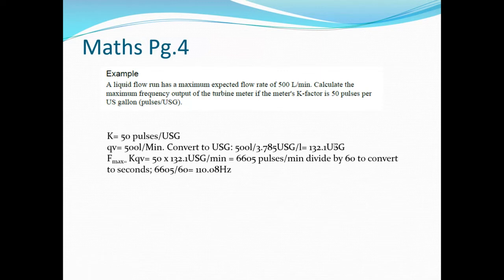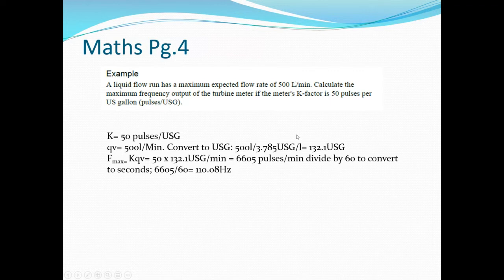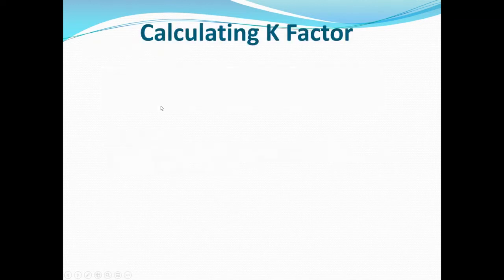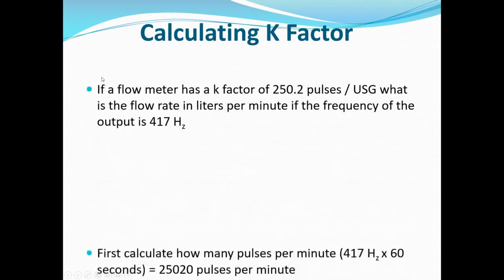Since frequency is counted in seconds, we convert: 50 pulses/gallon times 132.1 gallons/minute equals 6,605 pulses per minute. Dividing by 60 gives 110.08 hertz — that is, 110.08 pulses per second representing 500 liters per minute. The key conversions to be conscious of are gallons-to-liters and seconds-to-minutes.